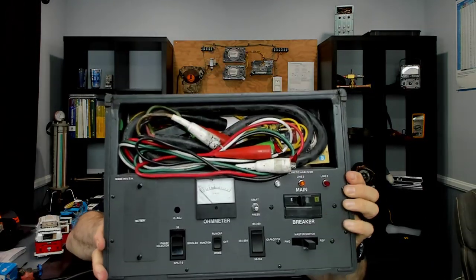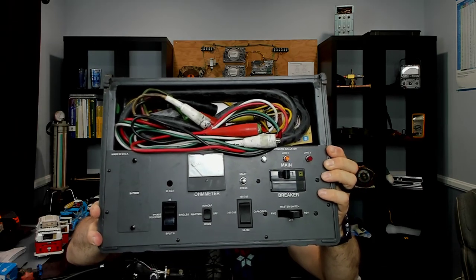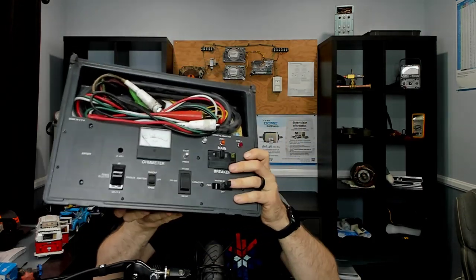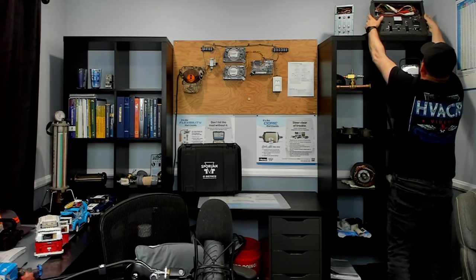Both of those are hermetic compressor analyzers, and what they do is give you the ability, via these dip switches, to simulate different capacitors. On a compressor, we typically need a certain size start capacitor to get it to start up. That box allows you to simulate different size capacitors to try to start a compressor. So if you go up to a compressor that's not running, we can put that analyzer on it and potentially start it up before driving to the supply house to buy starting components, because it could either be a bad compressor or bad starting components. That box allows you to simulate starting components.